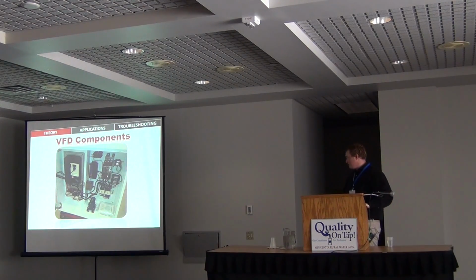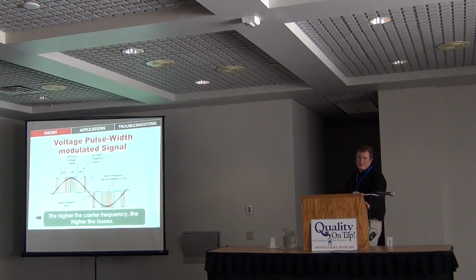If it's clean, obviously you don't need to clean it. Probably what they're getting at is they're going to replace the screens on the input side, where you have some sort of ventilation. They're going to clean those screens or replace them, vacuum it out, make sure it's clean. They might take a thermal imager or a temperature sensor and shoot the terminals of the VFD to make sure your connections are tight. How often to do it really depends on your situation.